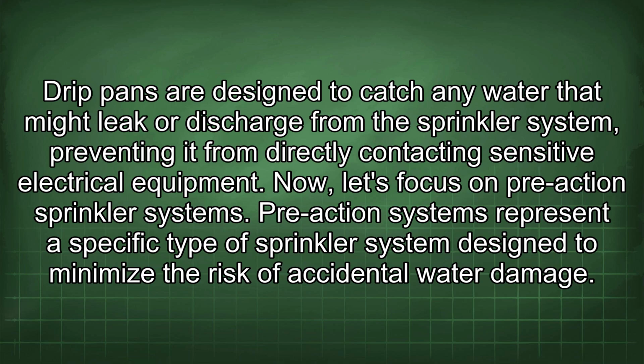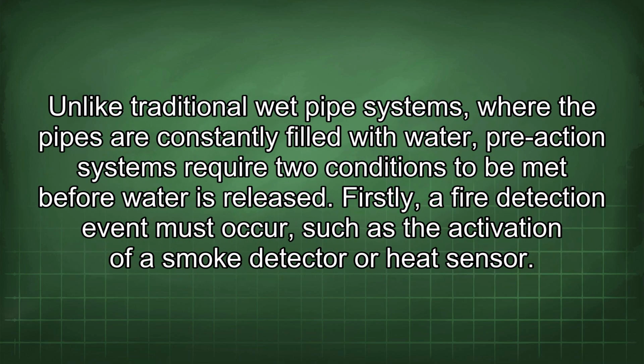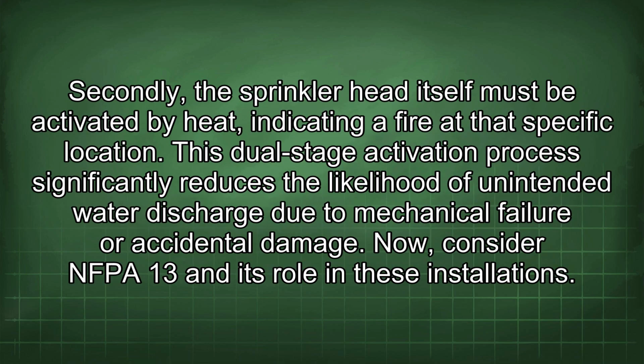Pre-action systems represent a specific type of sprinkler system designed to minimize the risk of accidental water damage. Unlike traditional wet pipe systems, where the pipes are constantly filled with water, pre-action systems require two conditions to be met before water is released. Firstly, a fire detection event must occur, such as the activation of a smoke detector or heat sensor. Secondly, the sprinkler head itself must be activated by heat, indicating a fire at that specific location. This dual-stage activation process significantly reduces the likelihood of unintended water discharge due to mechanical failure or accidental damage.